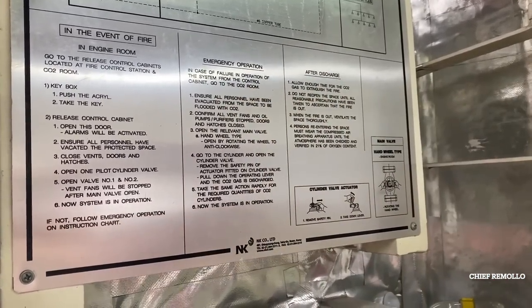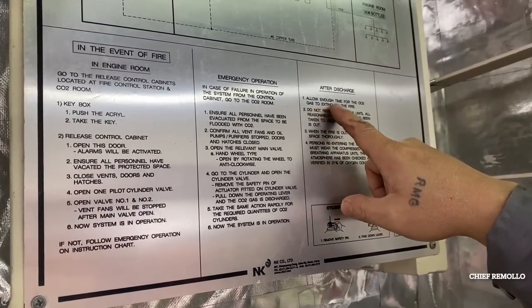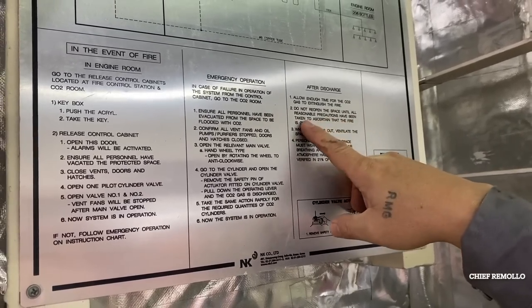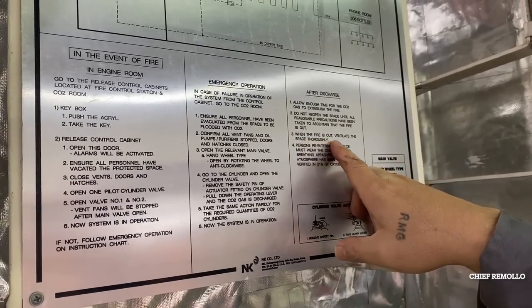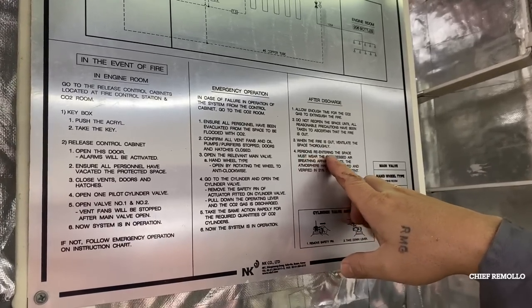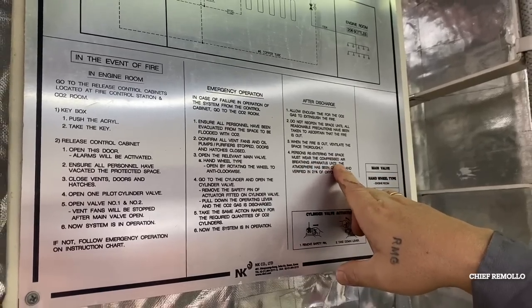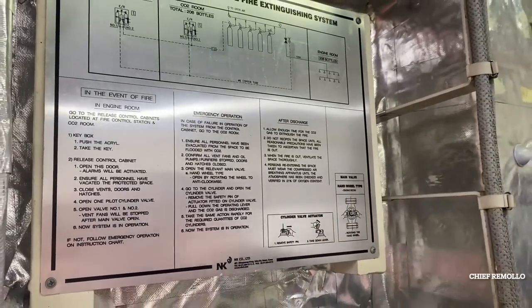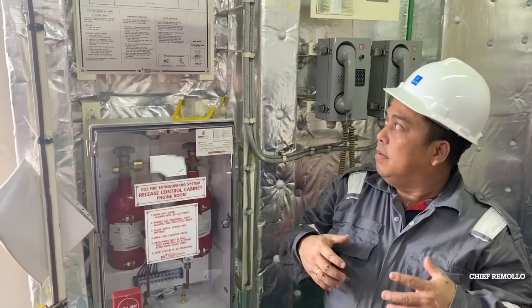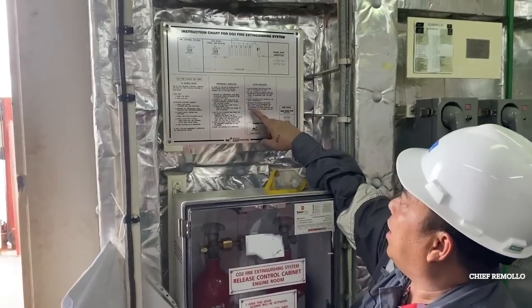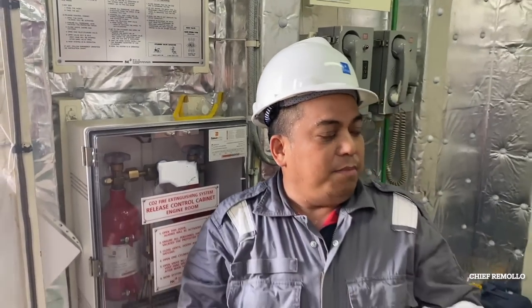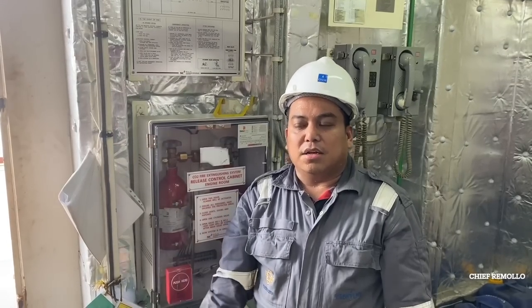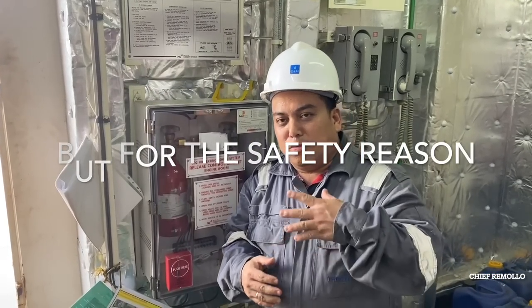After discharge, allow enough time for the CO2 gas to extinguish the fire. Do not reopen the space until all reasonable precautions have been taken to ascertain that the fire is out. When the fire is out, ventilate the space thoroughly. Any person entering the space must wear a compressed air breathing apparatus until the atmosphere has been checked and verified at 21 percent oxygen content. So, the person entering must have SCBA. We do not know the oxygen level, so we need to test with an oxygen analyzer. But for safety reasons, you must wear SCBA.